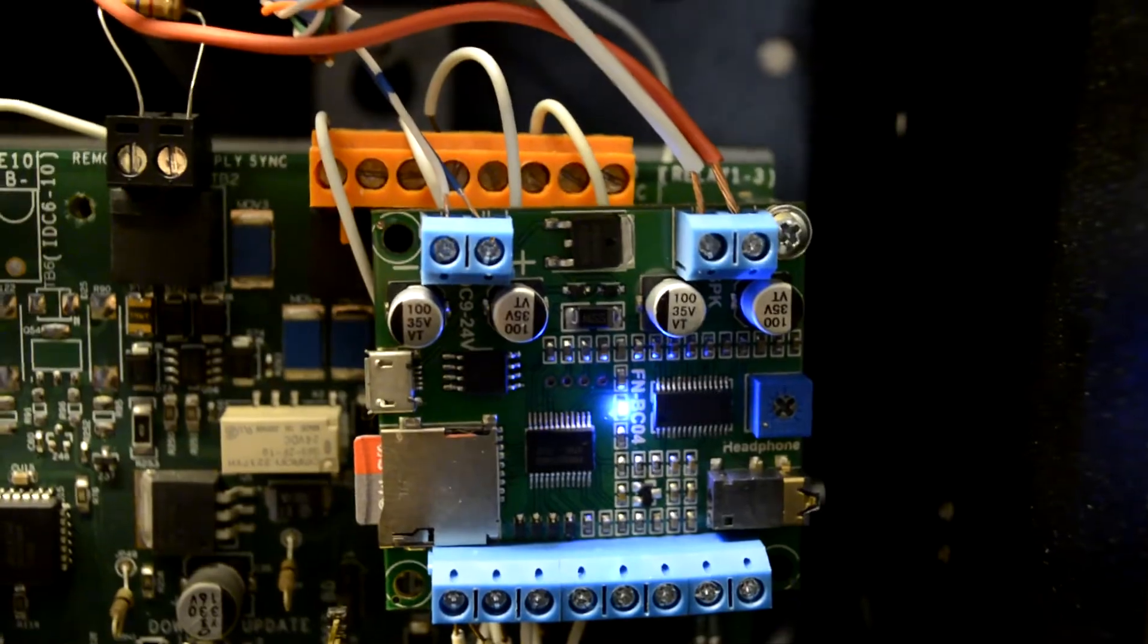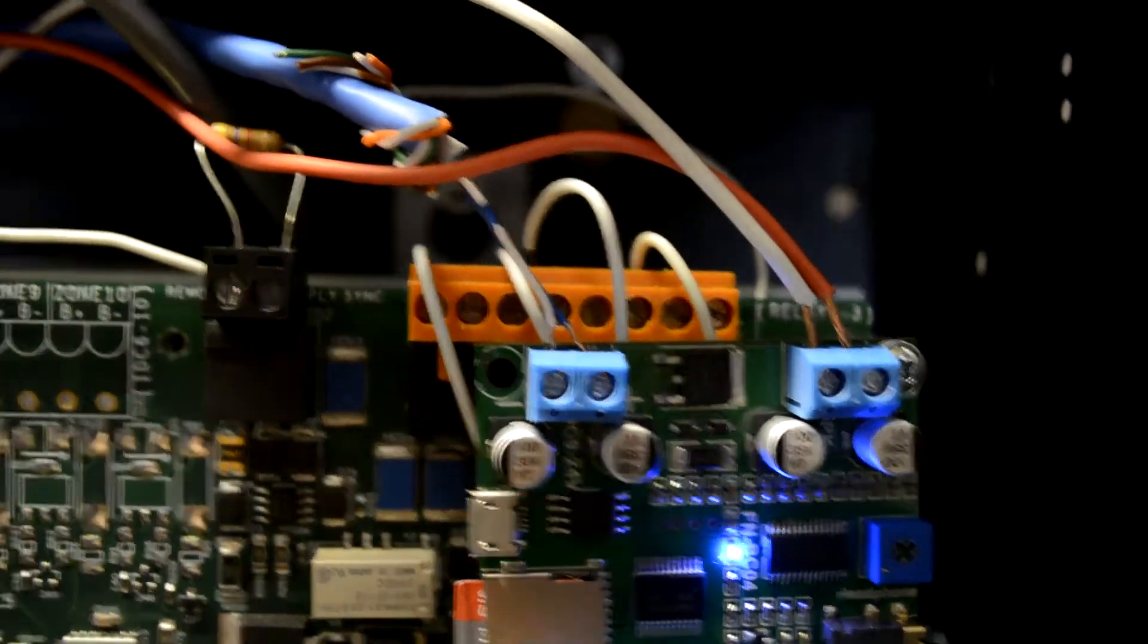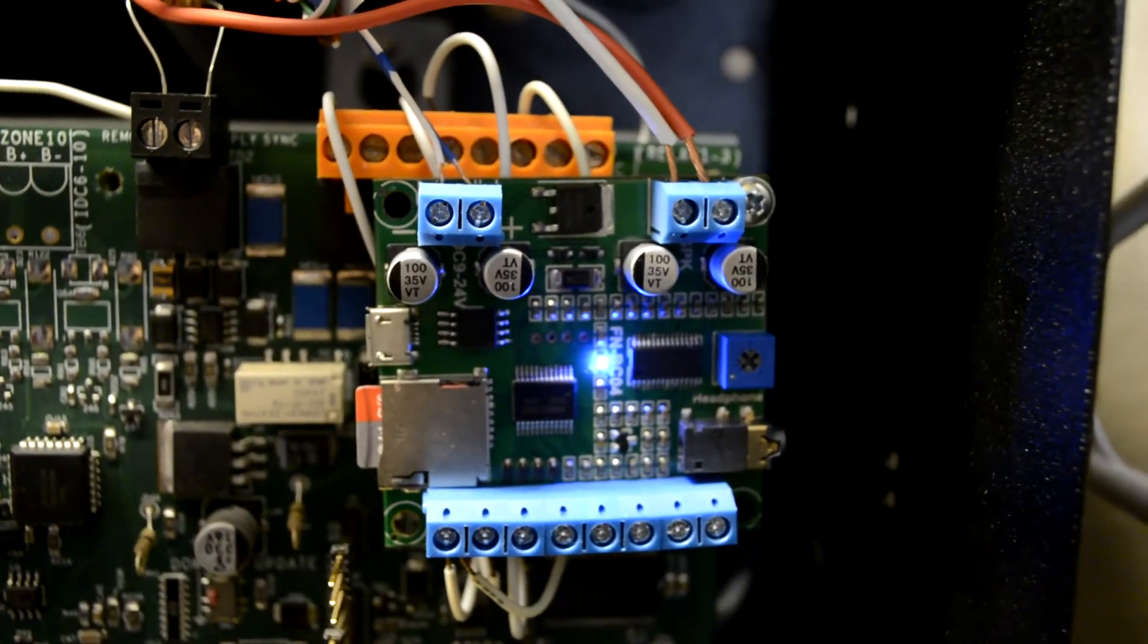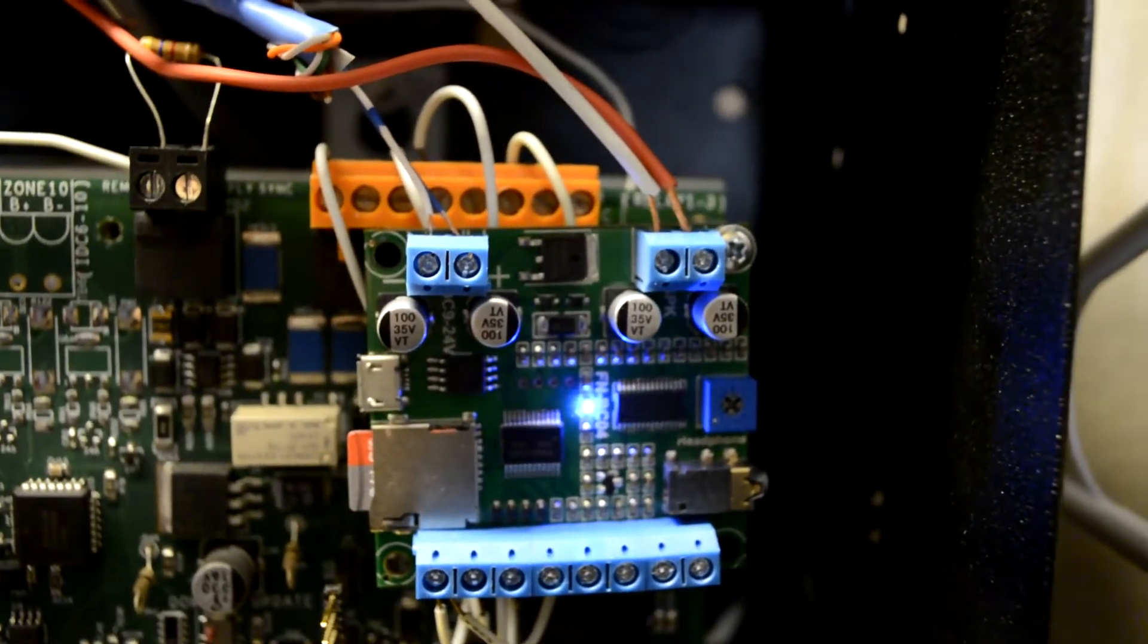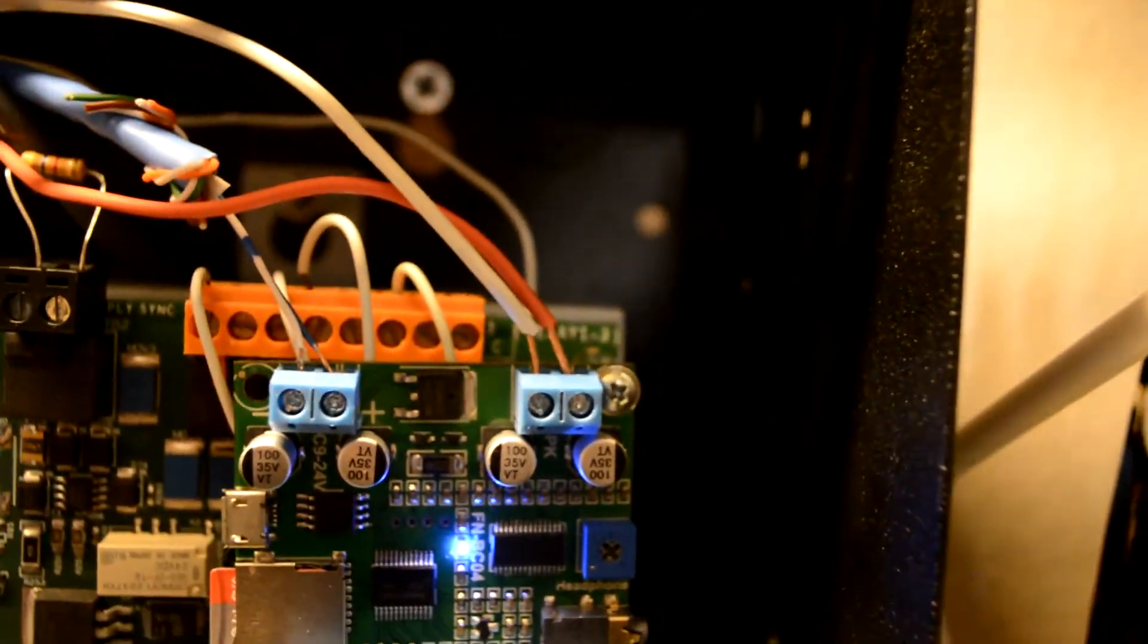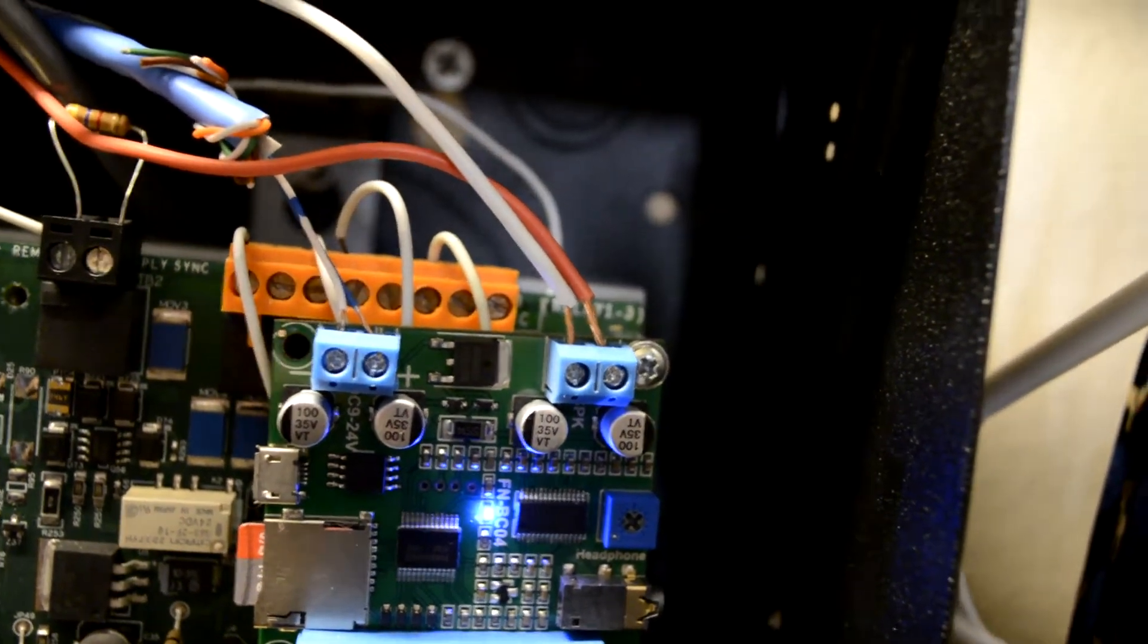The way this is wired into the panel is we have the 24 volts resettable power coming in from the panel on these two terminals. Then on this side is what would technically be considered a NAC. This little chip has an onboard 24 volt 10 watt amplifier. The speaker strobe is set to 25 volts, and I've got it set to the 2 watt maximum. This little potentiometer here on the side controls the volume of that amplifier locally. The speaker itself is wired into this, so this is acting in the capacity of an extra NAC. And then the strobes are going to be wired into NAC 1.